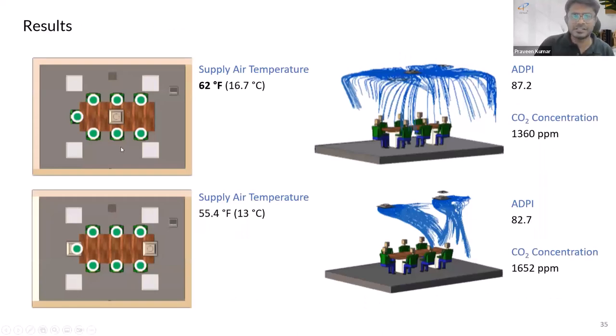The first thing is both provided the same level of comfort, all occupants are in green. But the interesting thing is the first design configuration only needed a supply air temperature of 62 Fahrenheit to achieve this level of comfort. But the second design configuration, which lacks the momentum, directly drops the draft into the occupied zone.